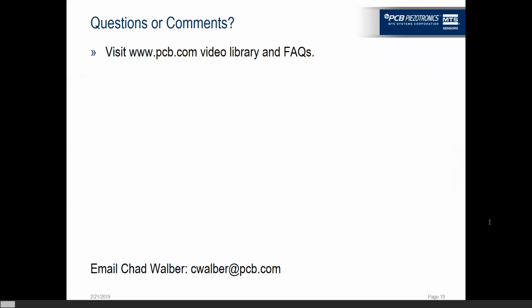So I do have a question here: calibrating audiometers. Do you need to correct for temperature, humidity, and barometric pressure? I would say it depends on your calibration method. I'm assuming you're saying calibrating the audiometer, not calibrating the microphone. Is that correct, Dave? Okay. I don't know what the audiometer standards call for. I believe the last time I read them, when you performed your calibration, you had to take note of all of that, but you did not have to correct for all of that.